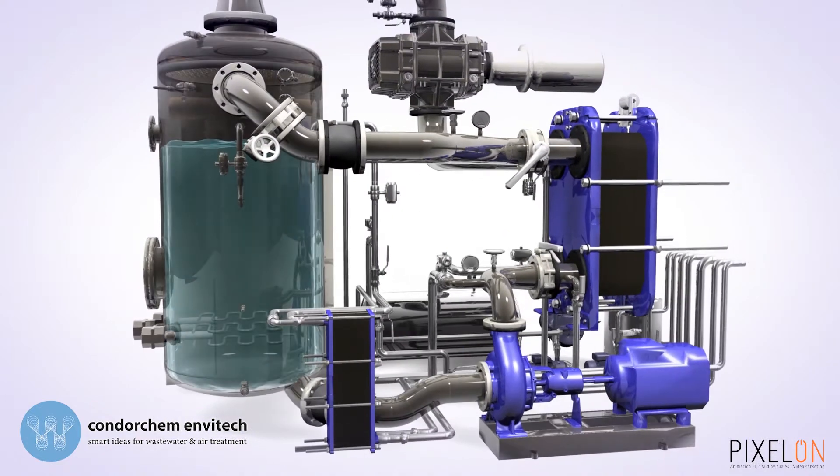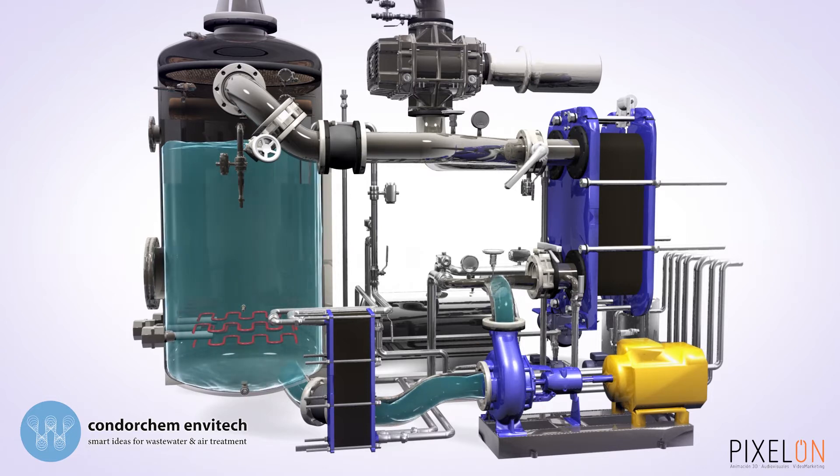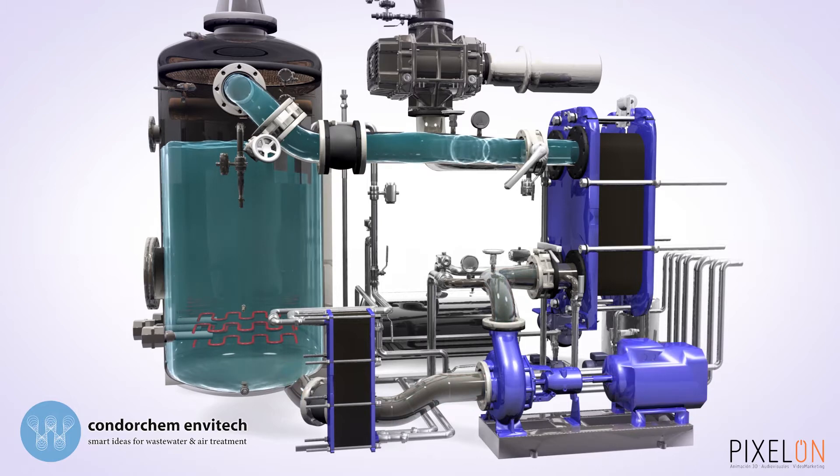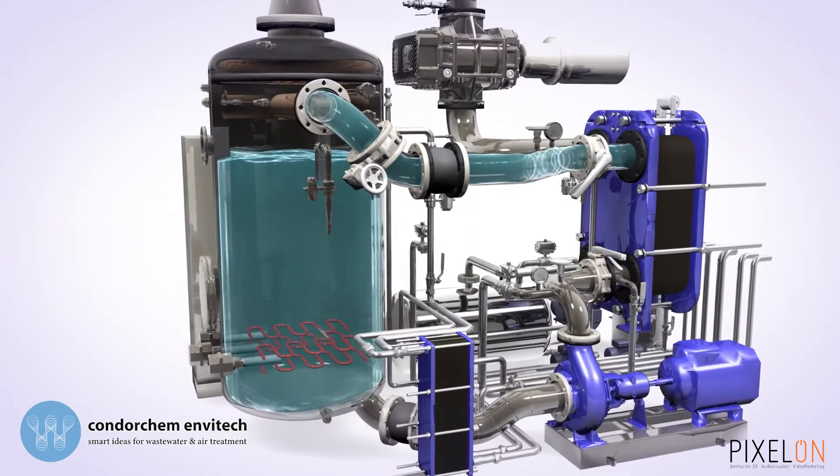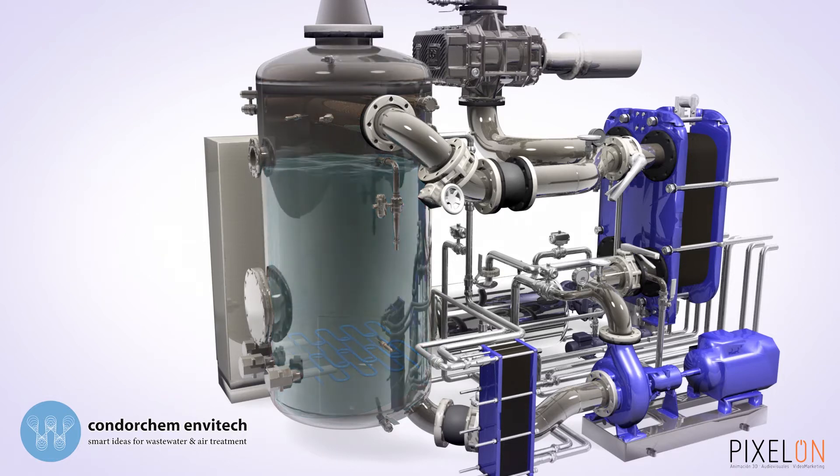the recirculation pump and the electrical resistors start working, to reach an operating temperature of 60 degrees Celsius. At this point, the resistors stop and the vacuum system reaches a value of 240 mbar in the evaporation boiler.